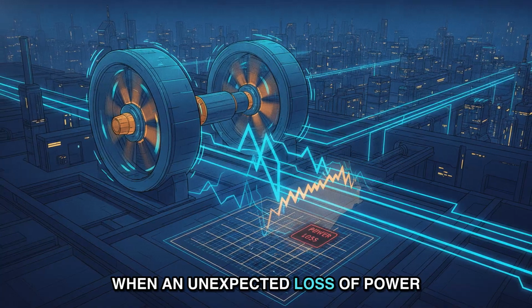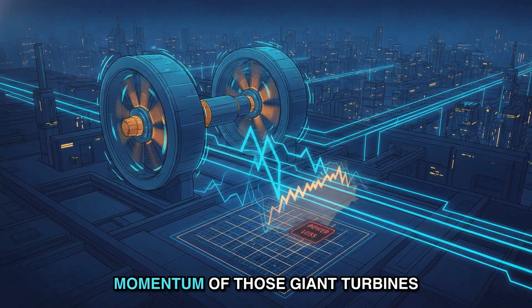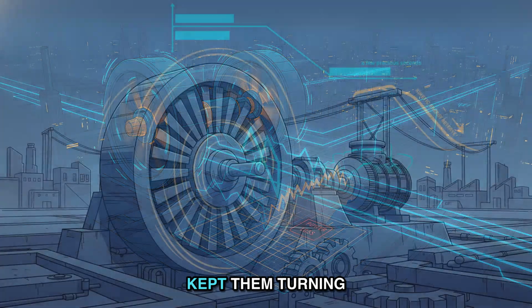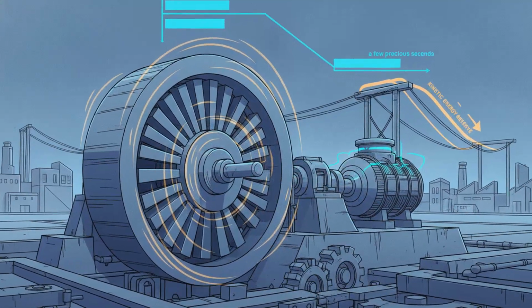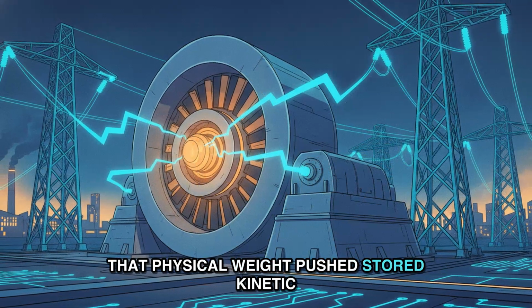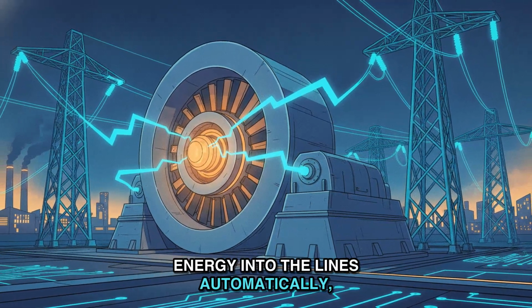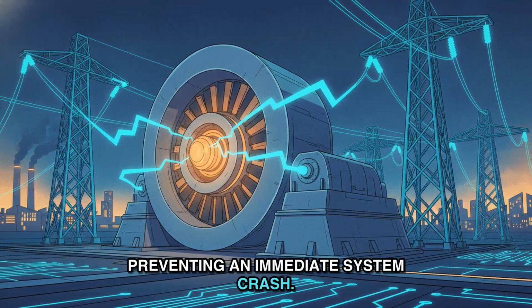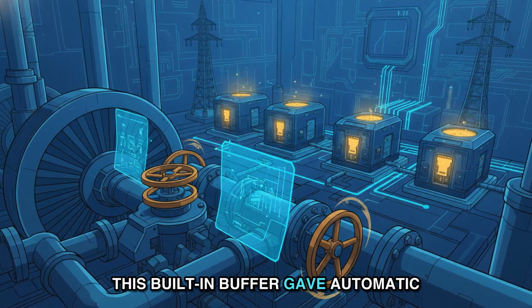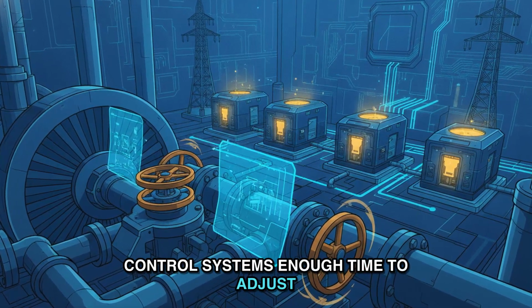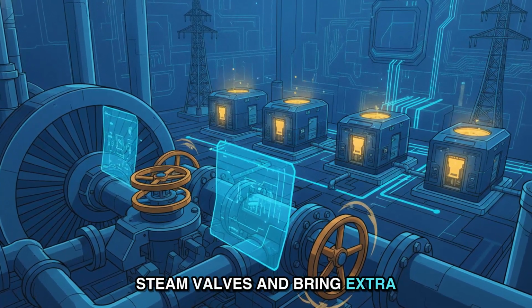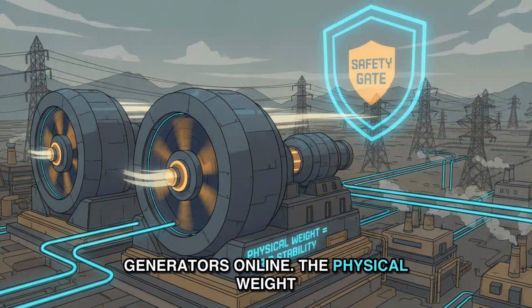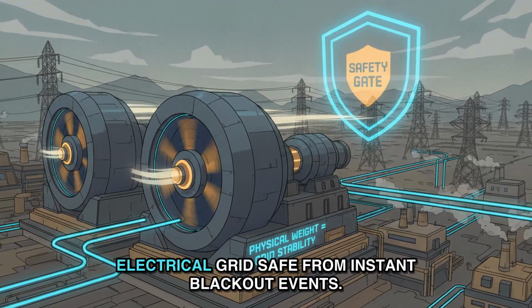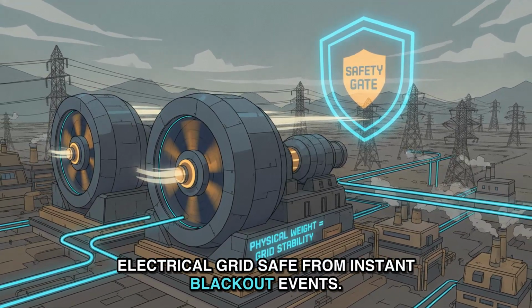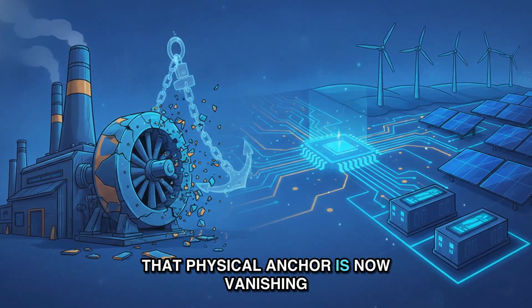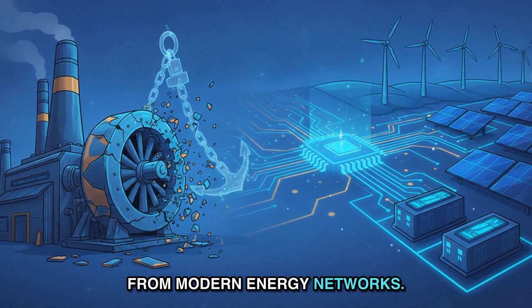When an unexpected loss of power generation happened, the spinning momentum of those giant turbines kept them turning for a few precious seconds. That physical weight pushed stored kinetic energy into the lines automatically, preventing an immediate system crash. This built-in buffer gave automatic control systems enough time to adjust steam valves and bring extra generators online. The physical weight of heavy machinery kept the entire electrical grid safe from instant blackout events. That physical anchor is now vanishing from modern energy networks.